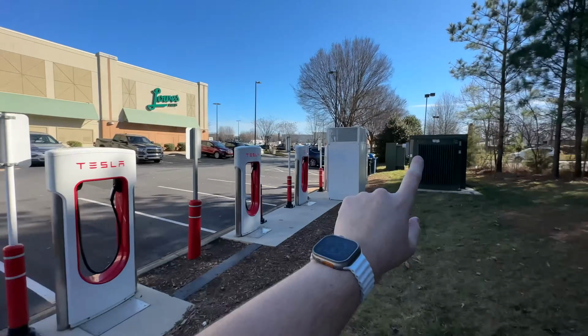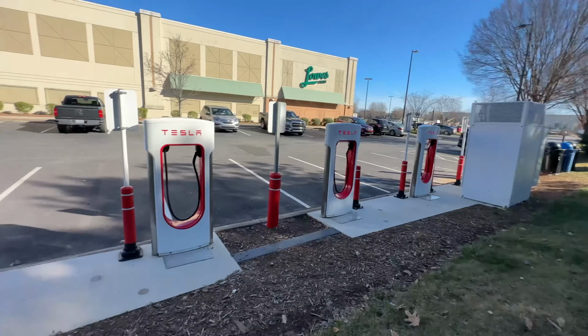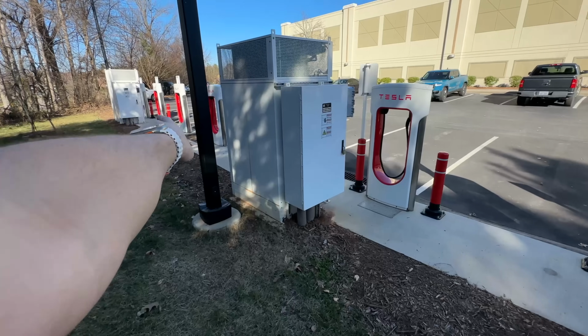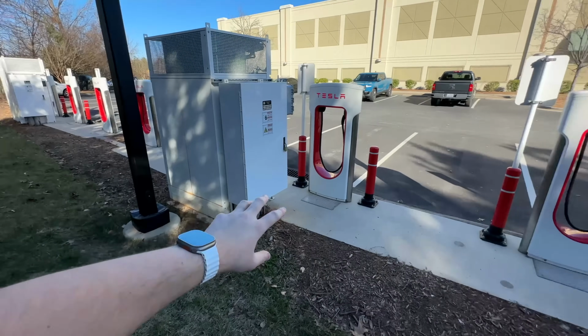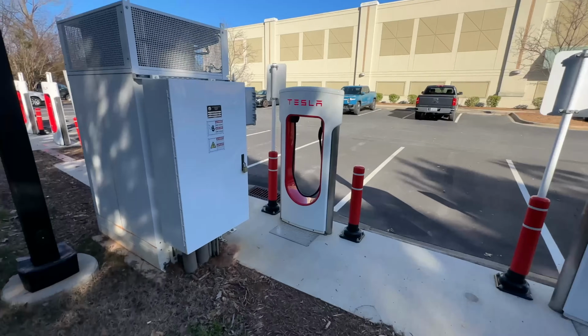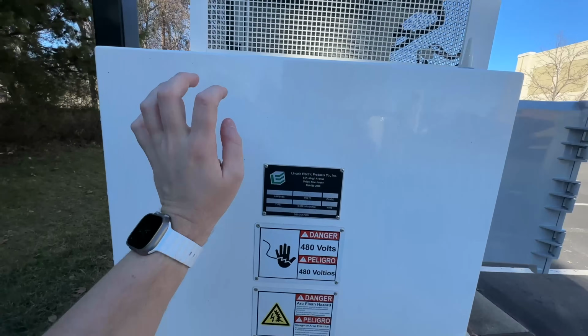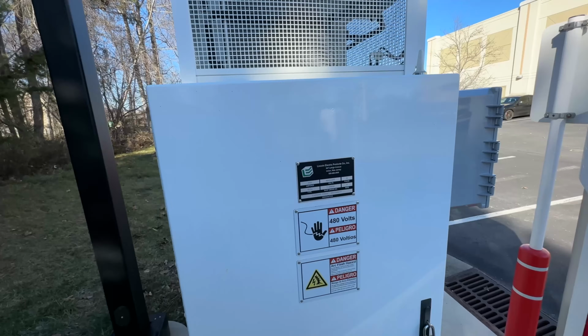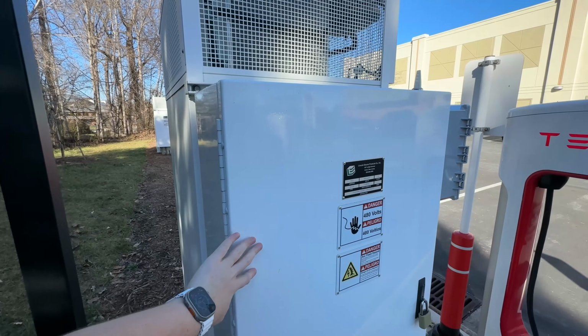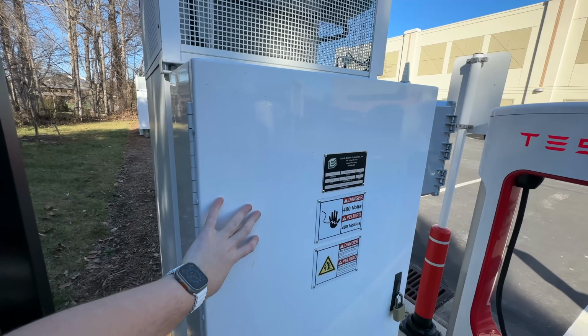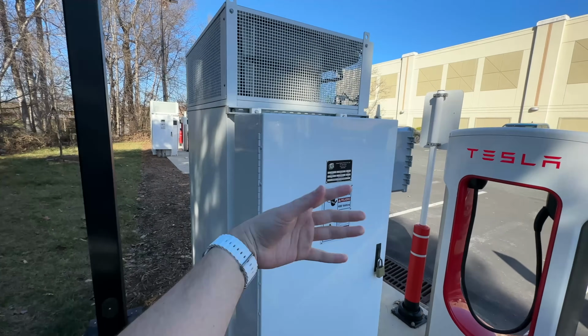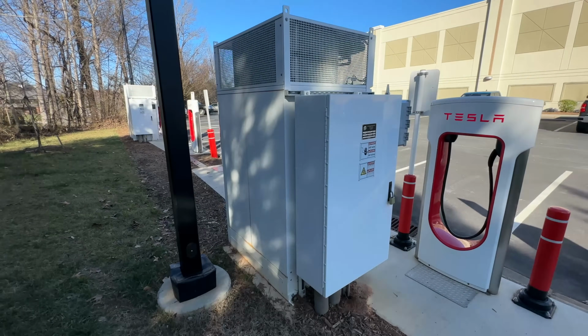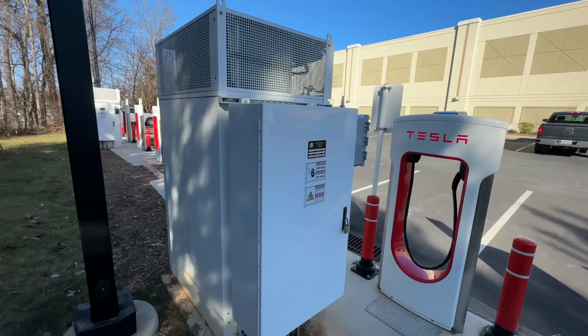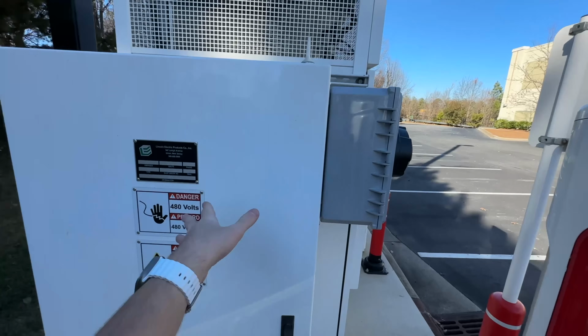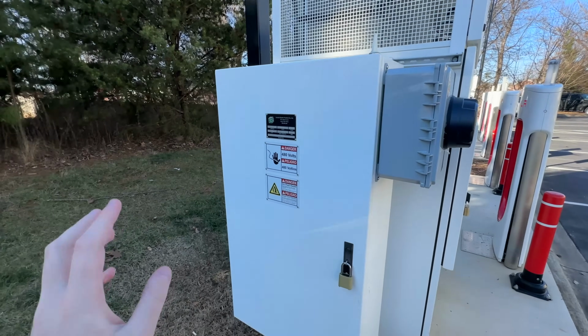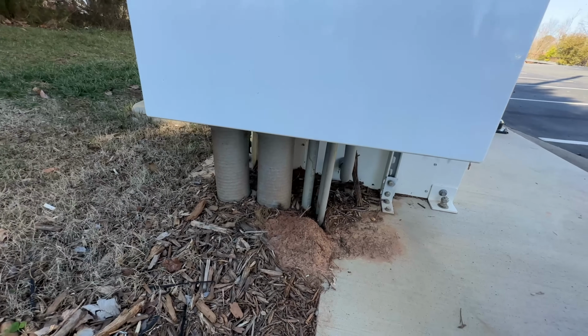From the transformer, like I mentioned, you have two 4-inch conduits going to each one of these—those are your only conduits for power. That's actually going into this box here. There are a couple different variations, but they're all 600 amp, 480, 277 rated disconnects inside this cabinet. It's kind of like a mini switchgear, if you watched my previous video—actually made by the same company, Lincoln Electric Products, in many cases, but not all. Down here, you can see these smaller conduits.